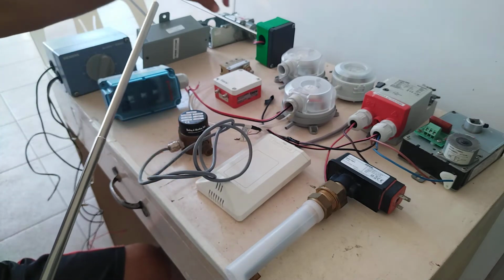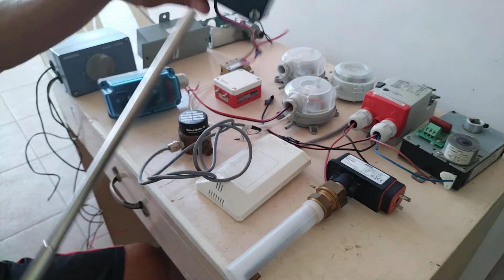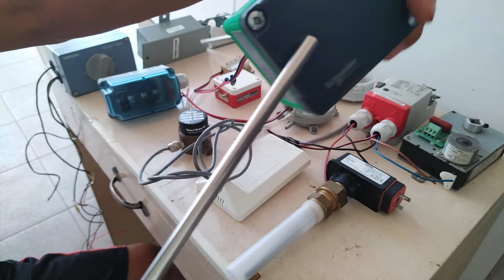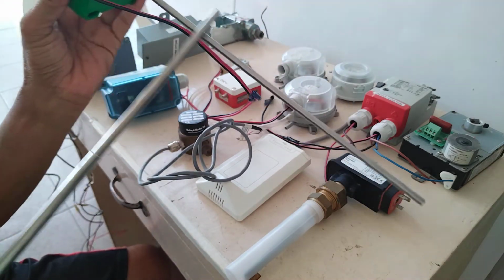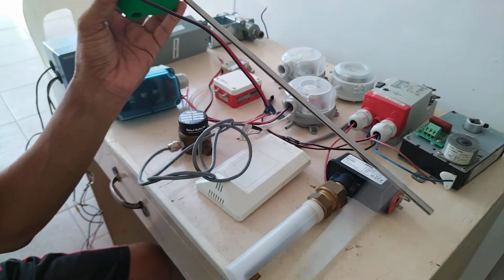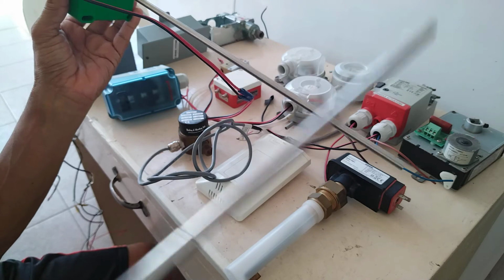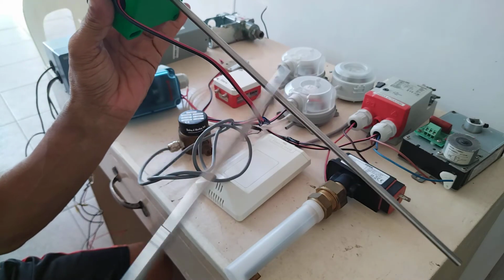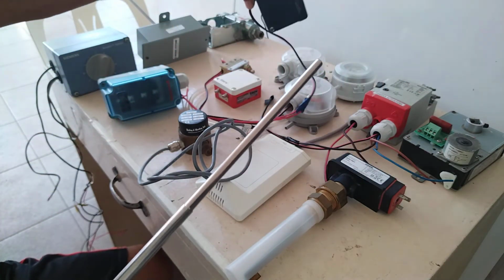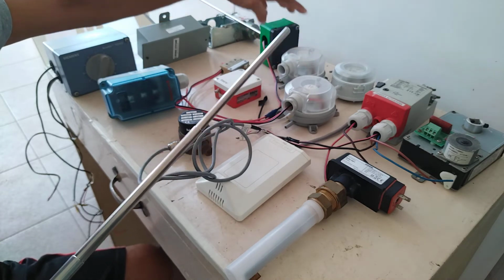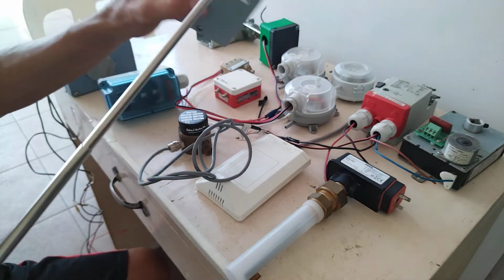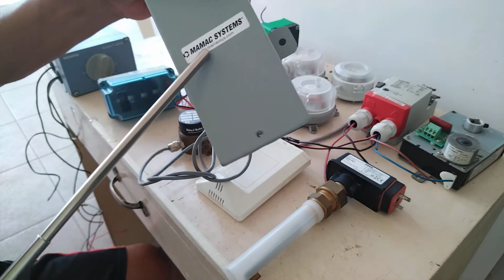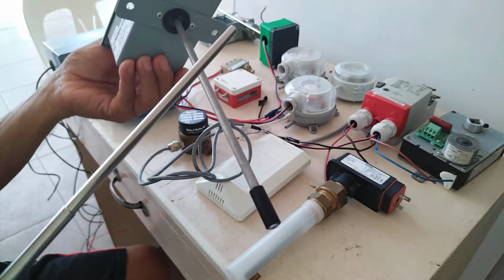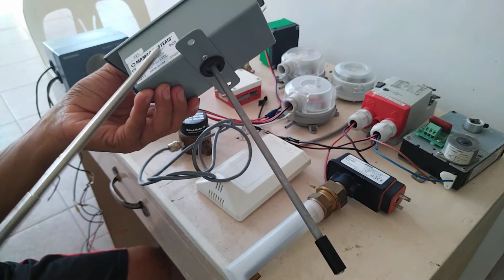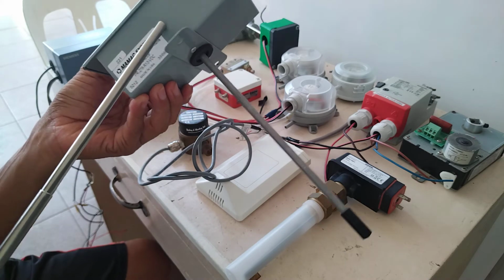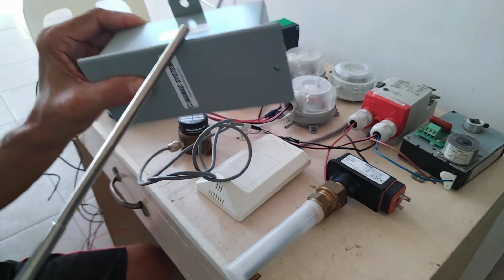Now, what I have here is a duct temperature sensor, okay? For the duct temperature sensor, all you need to do is drill a hole in the duct, then insert this probe. This probe will be the one to sense the temperature of the air passing in the duct, okay? Now, I also have here an absolute pressure sensor, okay? So, this one is a duct absolute pressure sensor. It will sense the pressure inside the air duct, okay?